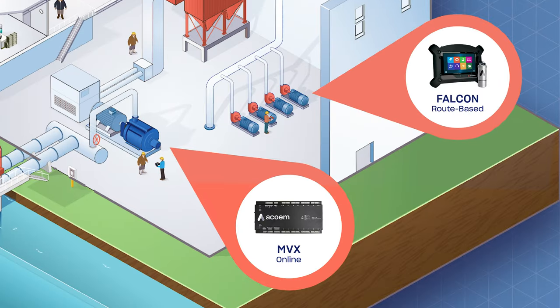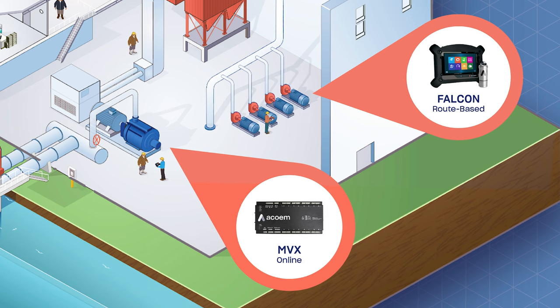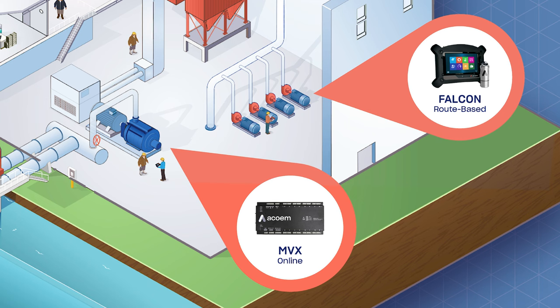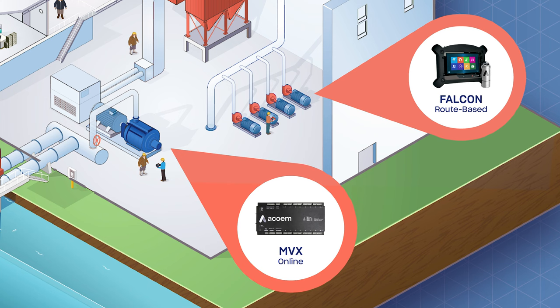The next system is a portable system for the circulating pumps down on the floor — very accessible. We all know that pumps, when installed and operated correctly, run with a high degree of reliability, so we can sample on a monthly basis and walk around to check them. One advantage of portable collection is that when we're there, we can also note the suction and discharge pressures to make sure the pump is actually operating on curve. Although vibration technology will tell us if they're cavitating, it's always nice to have eyes and ears around these rotating pieces of equipment.